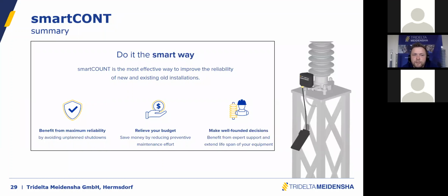If I were to summarize, I would speak about three important points for you. It is in your interest to minimize or avoid shutdowns and to increase the reliability of the surge arresters. Of course, this also has to do with your budget. You can reduce preventive maintenance effort and replacement of surge arresters if they are not damaged or bad. You can keep them inside the substation and not exchange or replace them after a while. In the end, we will help you with that and give well-founded decisions. You can contact us over our support channel, and we will try to answer your questions properly.